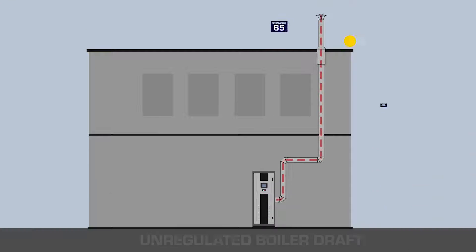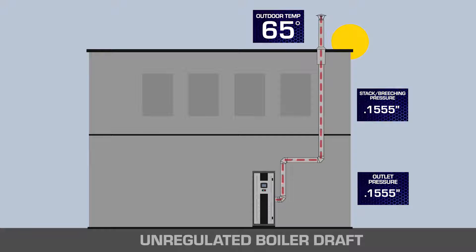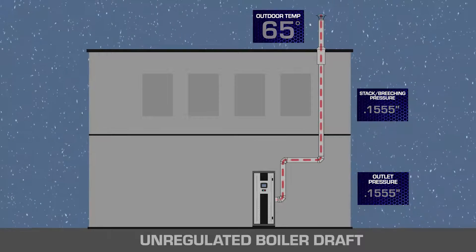System design for high efficiency appliances starts with vent sizing to make sure we have the correct diameter and stay inside the appliance manufacturer's published outlet pressure ranges at all times and all conditions. First, this needs to be done at a high ambient temperature, which is the least amount of natural draft available, and at a high firing rate to make sure we get full BTU use of the appliance even in a poor draft condition scenario.